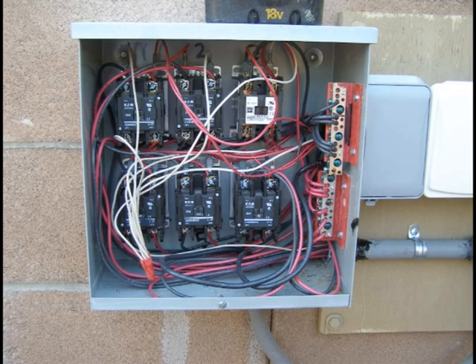How many violations did you come up with? This is by far the most dangerous code violation I have ever seen. The owner said the unit worked fine and did not need repairing, but I insisted before leaving that he at least let me label the cover: 'Live 240 volt bus bars enclosed. This panel is energized.' I did label it as such. I hope you have learned something from this, and I would like to remind you that there are codes for a reason. Thanks for watching, and have a great day.